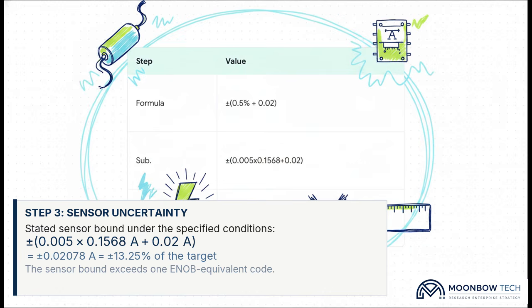Let's substitute our exact values. That's 0.005 multiplied by our 0.1568 amp target plus the fixed 0.02 amps. The result is an uncertainty bound of plus or minus 0.02078 amps. To put that in perspective, that is 13.25% of our entire target harmonic. That physical sensor uncertainty alone is larger than one entire ENOB-equivalent code. Your bias is literally eating your resolution.